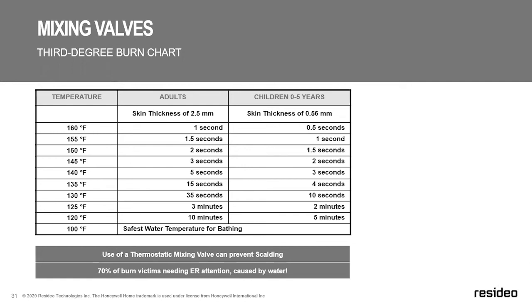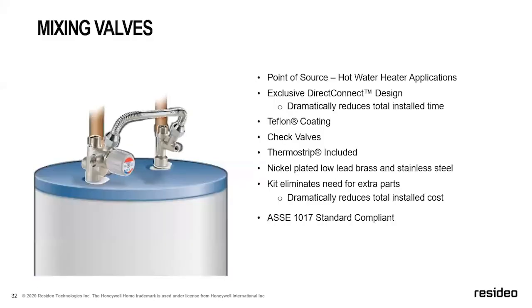But if you look to the right, it's only 2 minutes for a child, and that's because their skin is thinner. So we are going to have a thermostatic mixing valve, which can prevent scalding. 70% of burn victims needing ER attention, that is caused by water. So again, you can increase capacity of the water heater, minimize Legionella growth, and scald-proof the facility by having a mixing valve. Here's an example of what it looks like installed on top of a water heater.